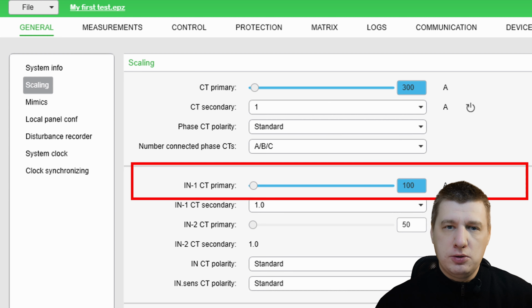In software, you should navigate to the General menu and Scaling view. You will see CT primary at the top for the phases, and further down you'll find the rated primary residual settings. Getting those ratios right is the only way your relay will know if the 5 amps at its terminals means normal load or a fault. Remember, never energize your primary circuits until you have double checked these scaling values.